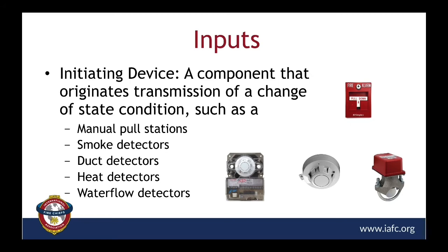So looking at smoke detectors, they detect visible or invisible particles of combustion, and particles of combustion is typically referred to as smoke. Now, looking at duct detectors, they detect the smoke or particles of combustion that is present in the air moving through HVAC ductwork. Now, these devices are designed to prevent smoke recirculation in certain areas of the building or spreading to the entire building. Now, looking at heat detectors, they respond to thermal energy. In other words, heat produced from the fire.